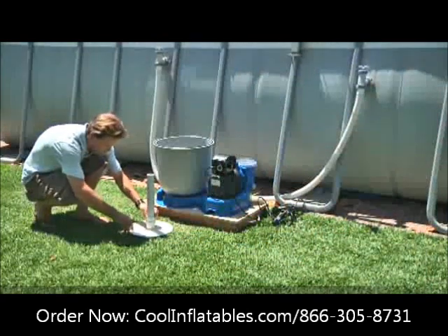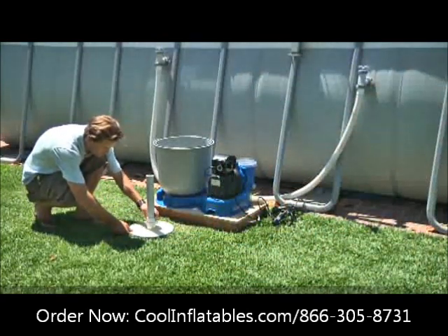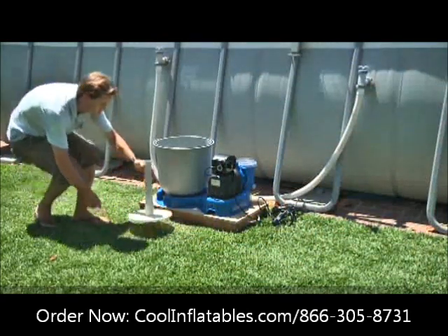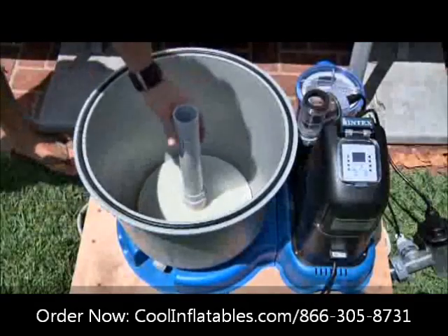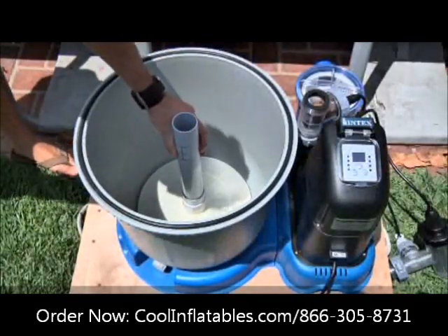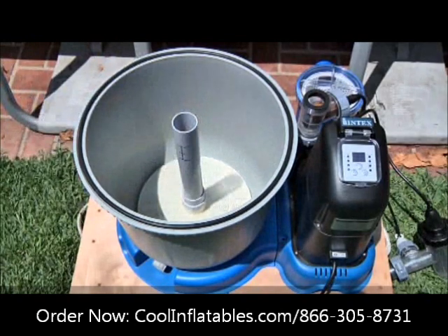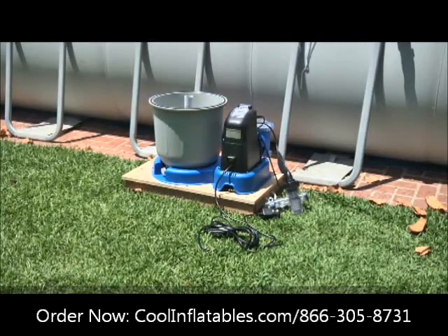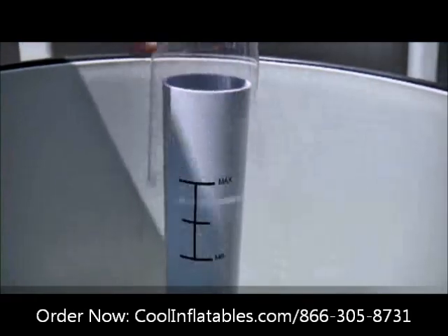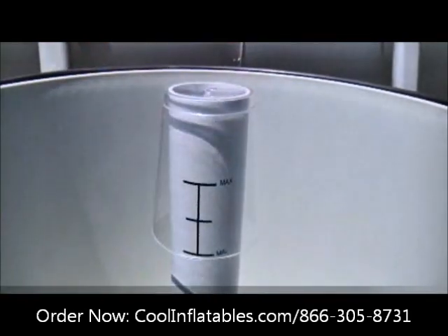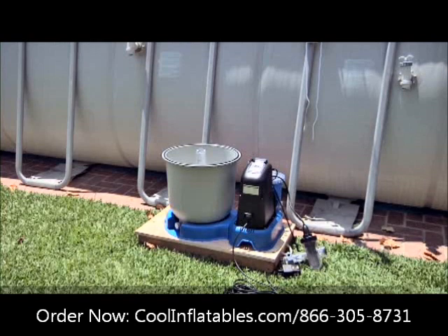Lay the filter grid on a flat surface and screw the center onto it by hand. Insert the assembly into the tank and fit it snugly into the bottom of the tank. The pipe must be vertical and centered. Before putting sand in the tank, cover the top of the center pipe to keep out sand. The recommended quantity of sand is between 88 and 110 pounds.